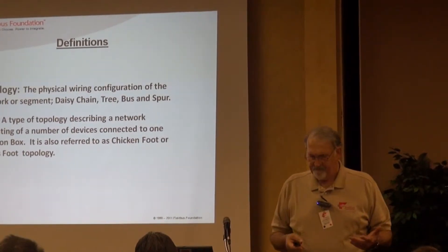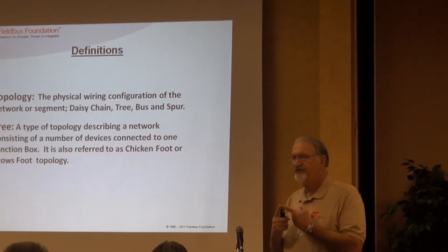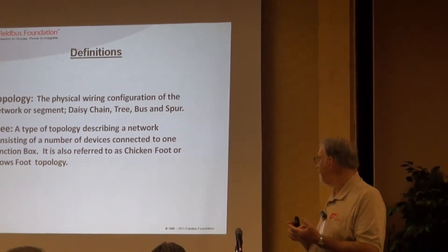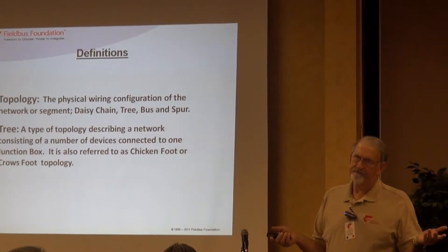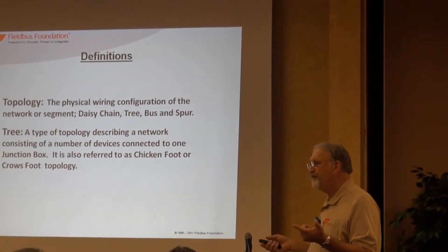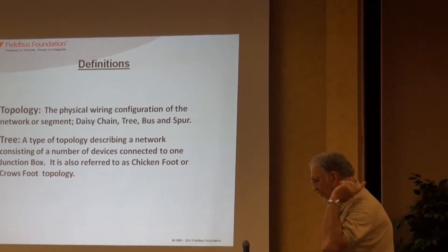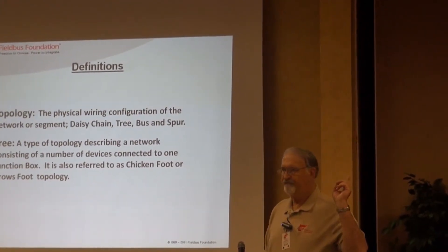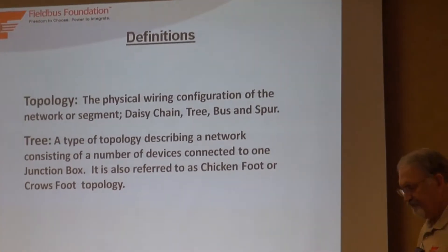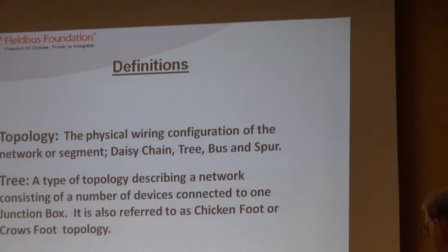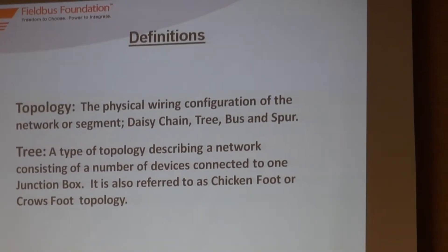Topologies - there are four basic kinds and a couple of variations: daisy chain, tree, bus with spurs, and you can actually have point-to-point if you so desire. Tree is the one we normally wind up using, and it's very similar to the 4-20mA world where you run an equivalent of a home run - this being the trunk - out to the field, to a device coupler or junction box, and then spread out from there. You can also call it chicken foot or crow's foot.